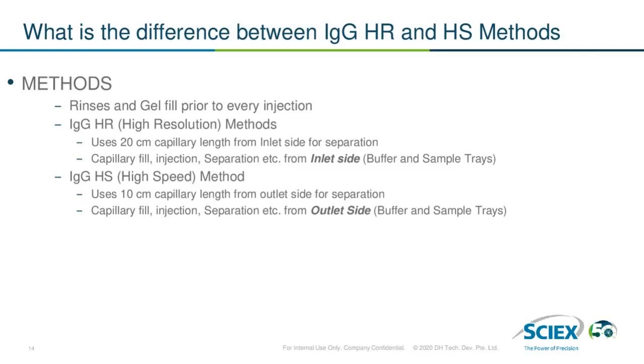Whenever you are running the high resolution method, we use a 20 centimeter capillary length from the inlet side for the separation, and all the buffers should be filled in the inlet buffer trays. For the IgG high speed method, we use a 10 centimeter capillary length from the outlet side for separation, and we keep all the buffers required on the outlet side.